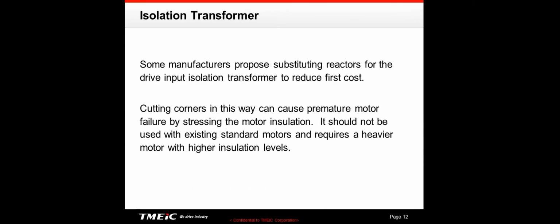I believe that all medium voltage drives should have an isolation transformer. Now, some people would disagree with me about that, and it has become more popular in recent years to use what they call a direct-to-drive solution, in which you do not have an isolation transformer. But there are many advantages of an isolation transformer, and my personal opinion is, don't cut corners. Get a drive that has a full isolation transformer.